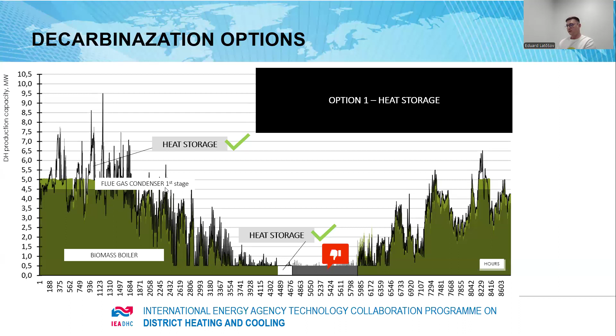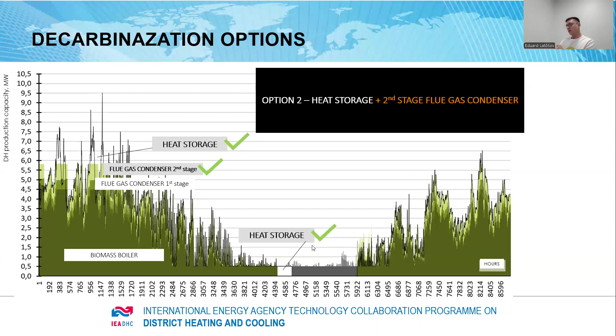The second option is to install a second-stage flue gas condenser, which increases heat output from the boiler. We can cover peaks with additional heat storage, but in this case the storage doesn't need to be as large compared to a solution without the second-stage condenser. Still, the problem with summer load remains.